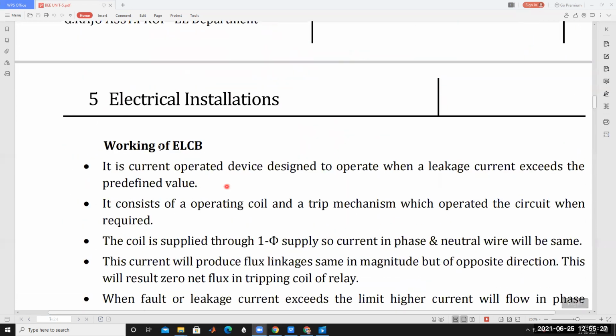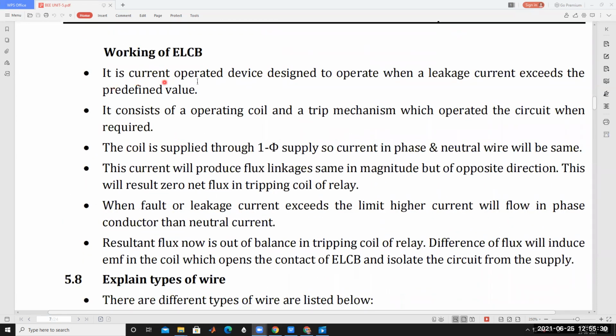Working of the ELCB: it is a current operated device, designed to operate when a leakage current exceeds the predefined value. That is called the normal operating value. A small amount of leakage current is not a dangerous fault, but as it keeps increasing, after some time it will become a dangerous fault.